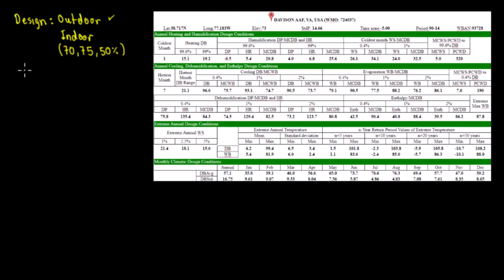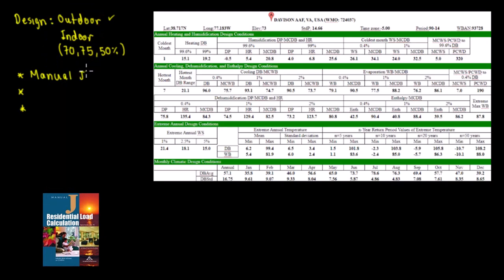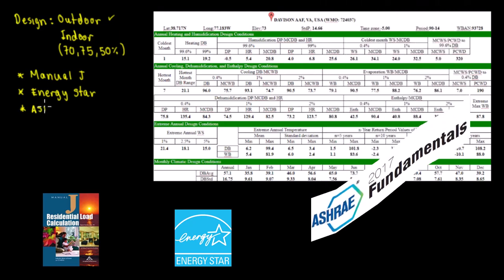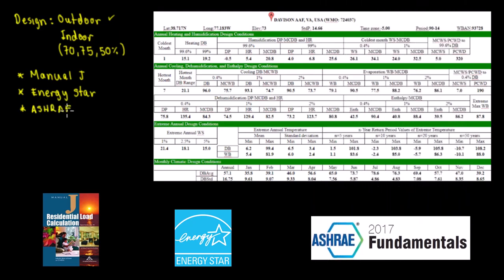On the other videos we explained that if we don't know the outdoor conditions we have three different sources. Source number one is Manual J — we'll put the link in the description below. Number two is Energy Star. And number three is ASHRAE Fundamentals — they call it ASHRAE weather data. For this video we're specifically going to be talking about the ASHRAE weather data.